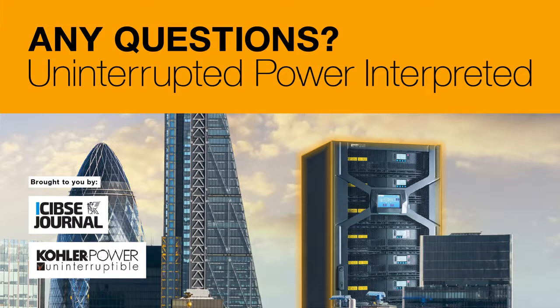We're just about coming out of time here. I'll see if I can select one more question that you can quickly answer. Maybe one from Huzaifa, and Huzaifa asks: is there any risk of dangerous gases building up from recharging VRLA batteries in large installations? The simple answer is yes, but the amount of gas depends on how the batteries are performing. There will be, from a VRLA battery, a small leakage of gas in normal operation that has to be allowed for. But if there's a fault on the battery, yes, it will output hydrogen gas that has to be considered.